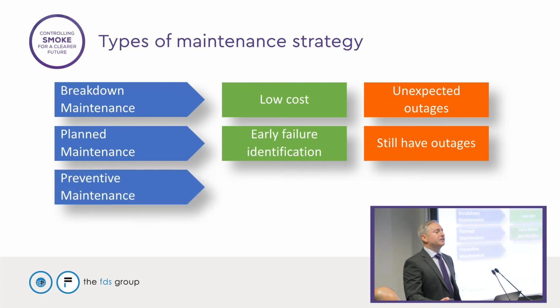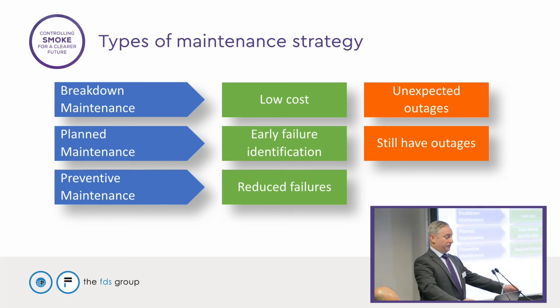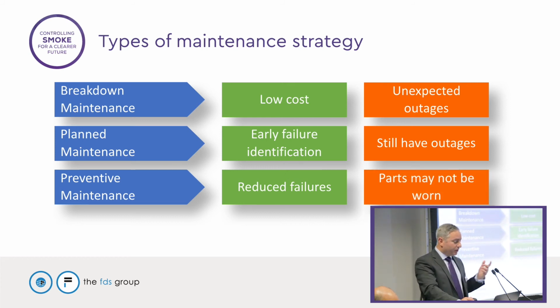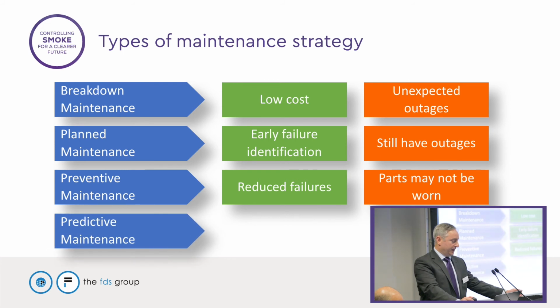Then we move towards preventive maintenance, and this is where we're actually replacing parts on a set interval. So we might be saying, oh, you've run your fans for the last 9 years. It's about time the bearings were changed, or it needs an overhaul, because we wouldn't want it to fail. The only downside with this is sometimes you're replacing parts and components that aren't worn, that aren't broken. So the industry, cross-engineering, has looked at this again and thought, well, how do we evolve from that? And we ended up with predictive maintenance, sometimes referred to as condition-based monitoring.